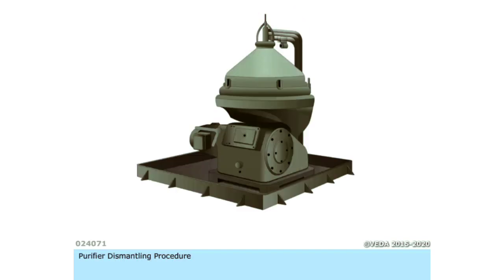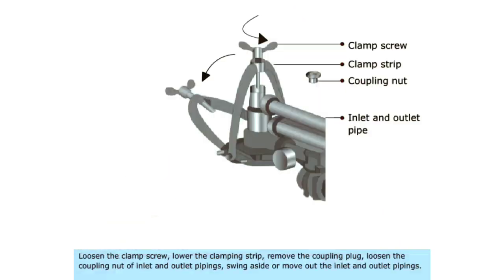Purifier Dismantling Procedure. Loosen the clamp screw, lower the clamping strip, remove the coupling plug, loosen the coupling nut of inlet and outlet pipings, swing aside or move out the inlet and outlet pipings.